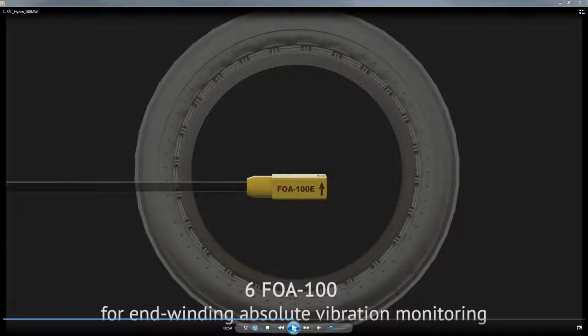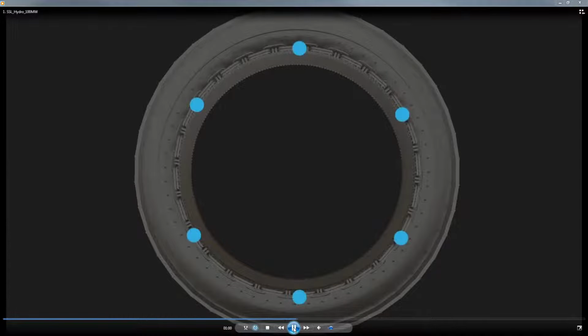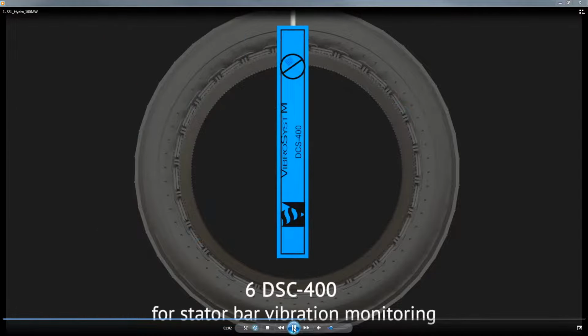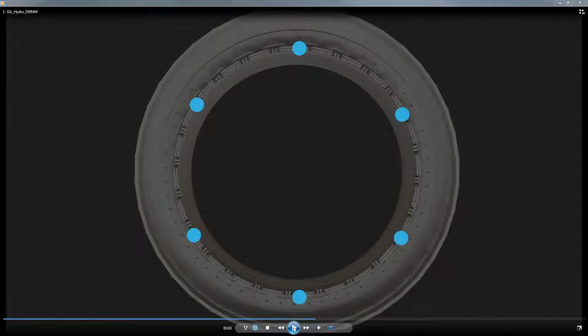But that doesn't mean that there aren't issues on hydro generators. And there's actually a paper I co-wrote with some Rio Tinto Alcan engineers where they had serious issues with their units, and the fiber optic accelerometers were very instrumental in showing what the problems were. So we recommend installing 6 on the end windings. And we also recommend putting 6 stator bar vibration probes.